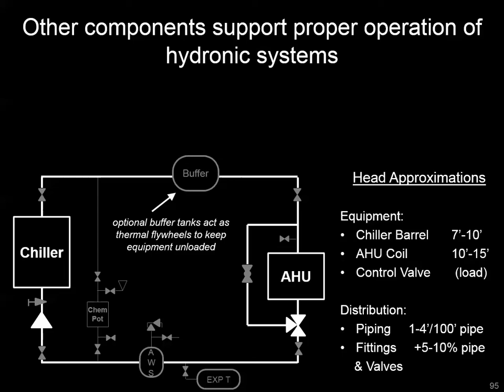You might also see for a smaller system something like a buffer tank. In a chilled water system where the chiller cannot go to a low enough load to handle all conditions, a buffer tank adds additional capacity, stretches out the on-off cycles of the chiller, and lets you leverage the thermal momentum of your piping distribution and the water inside rather than short cycling your equipment.